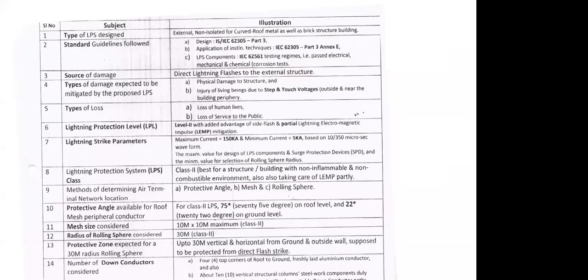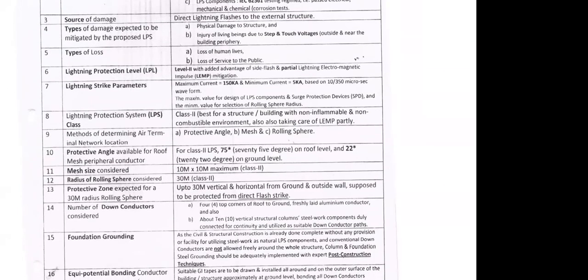Mesh size considered is 10 meter by 10 meter maximum for class 2. This class 2, class 3, all this is available in this particular IEC 62305. The radius of the rolling sphere is 30 meter. Protective zone expected for a 30 meter radius is up to 30 meter vertical and horizontal. I will explain this in the next picture. Number of down conductors considered is 4, from the top corners of the roof to the ground, with aluminum conductor, and you can use copper conductor also, depending on the design and the cost implication.